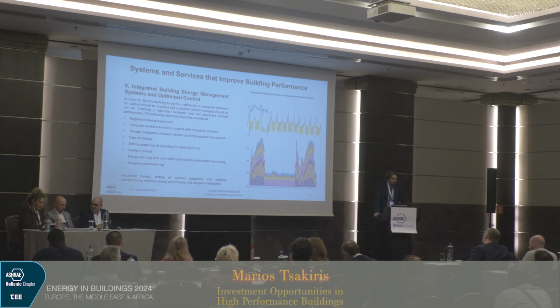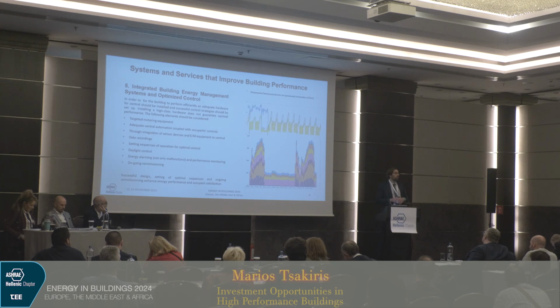So data recording, a BMS with energy management features is essential. Believe me, I had a case where we changed some chillers - they were old, we put in new chillers, optimized the sequence of operation, everything. We had the meters on, and the pumps were working - the internal pumps of the chillers were working. It was 3 kilowatts, okay, but it's 3 kilowatts, nobody would know in a new system.